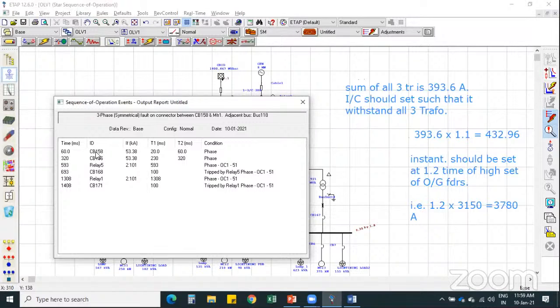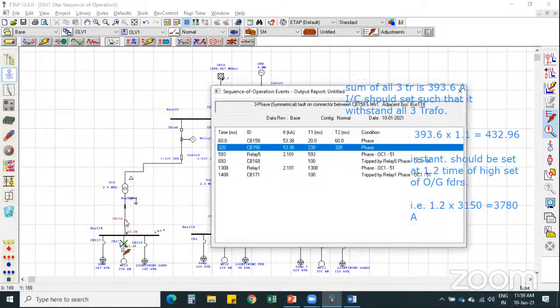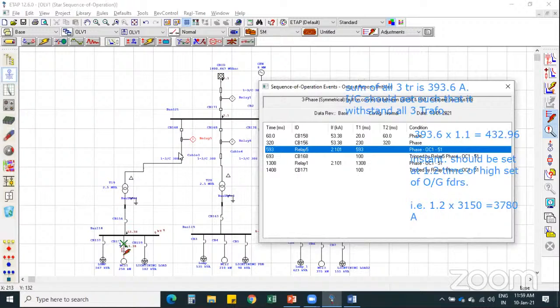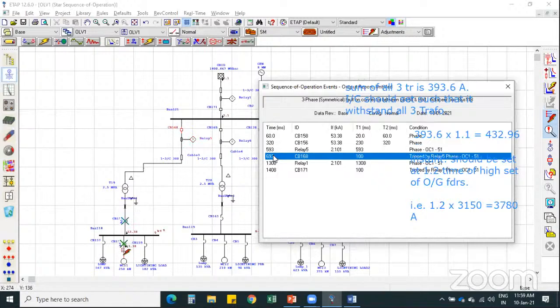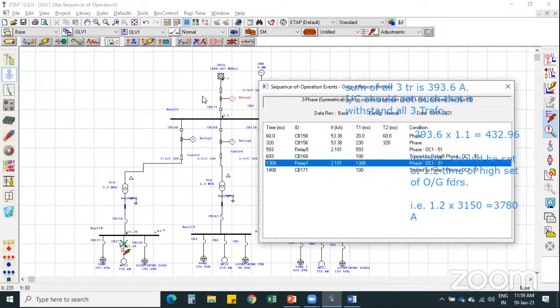As we have set instantaneous protection, considering the circuit breaker time of operation, the time of operation is 60 milliseconds. Then we have taken a minimum time delay of 200 milliseconds. So this breaker, highlighted in red, gets operated in 320 milliseconds. Relay 5, the primary relay, we have set for 600 milliseconds, so it operates at nearly 593 milliseconds, and considering the circuit breaker time, at 693 milliseconds. And at 1.3 seconds, the incomer relay operates.